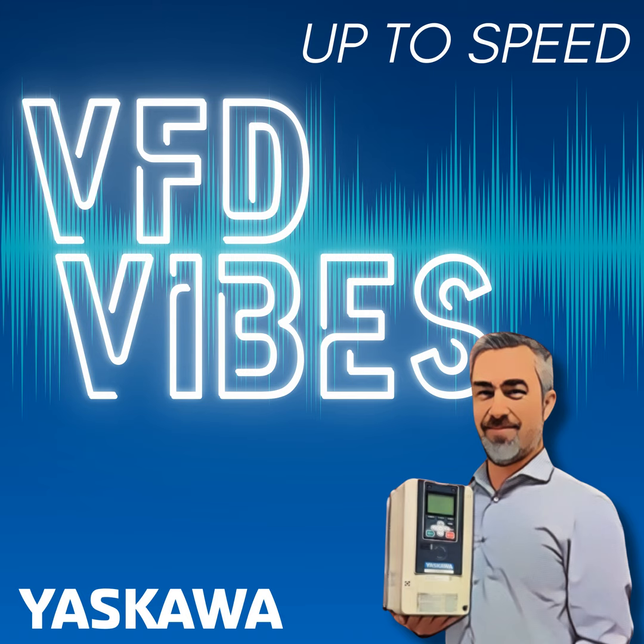Another benefit of monitoring energy is the ability to do further root cause analysis. For example, you could be chasing down a troublesome recurring fault, and you've looked everywhere in your process but can't find the culprit. But now, because you're monitoring the power coming into your drive and logging variables such as the DC bus ripple, you can actually determine when a problem might be due to something external to the process, such as the incoming power from the utility.